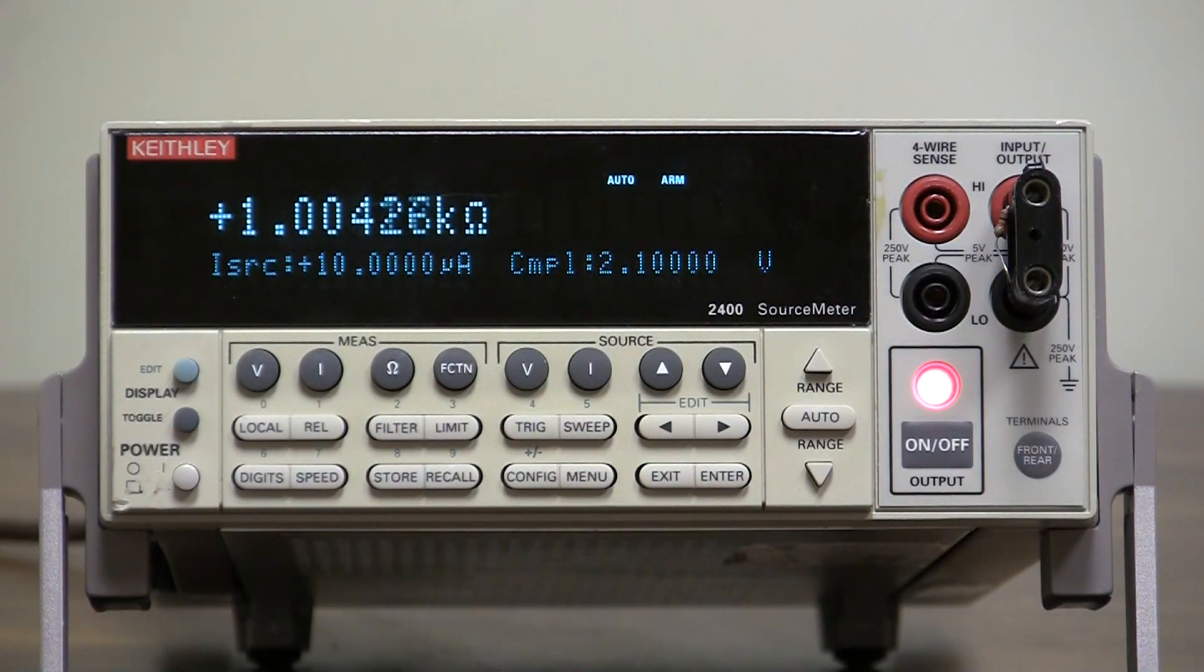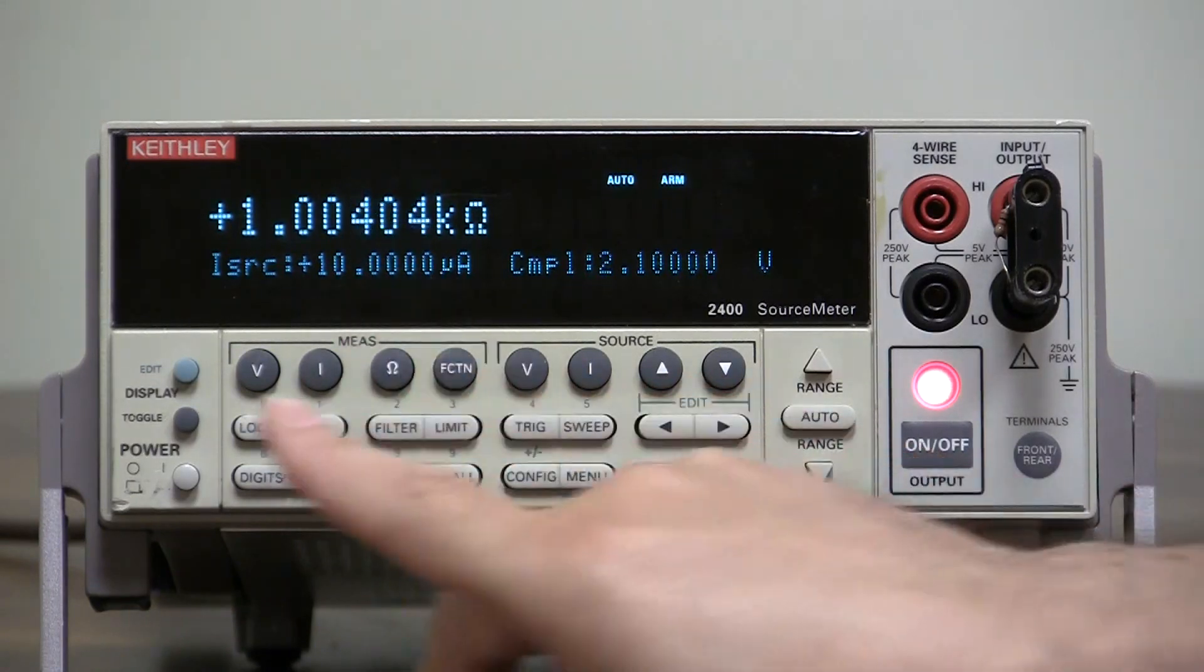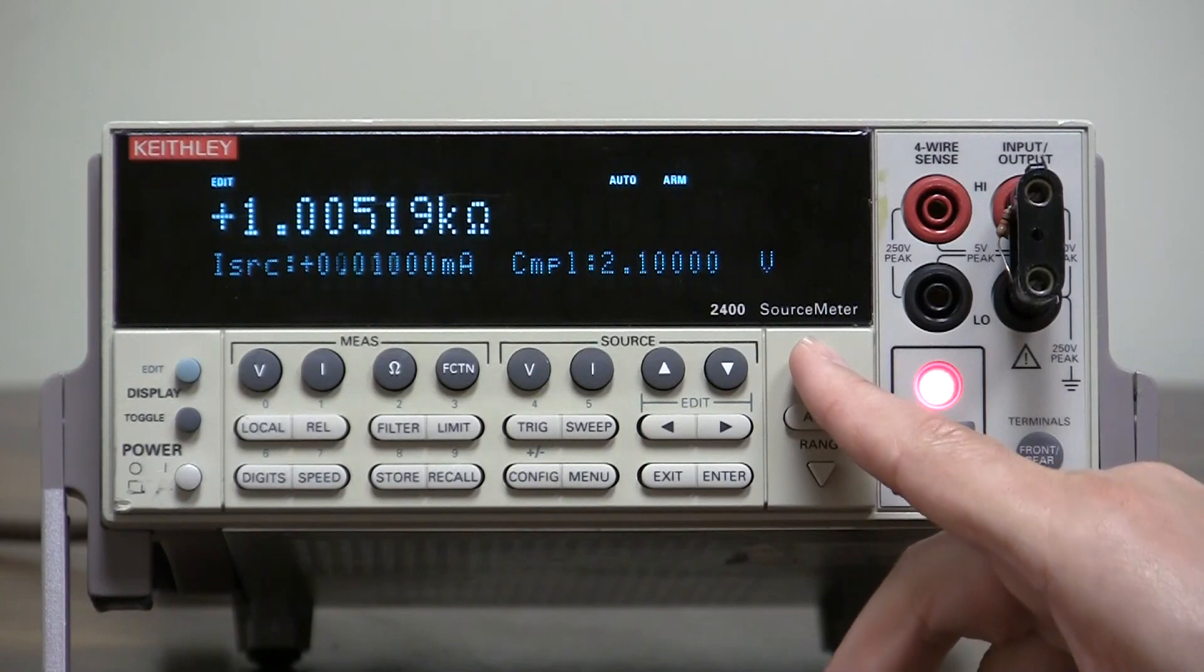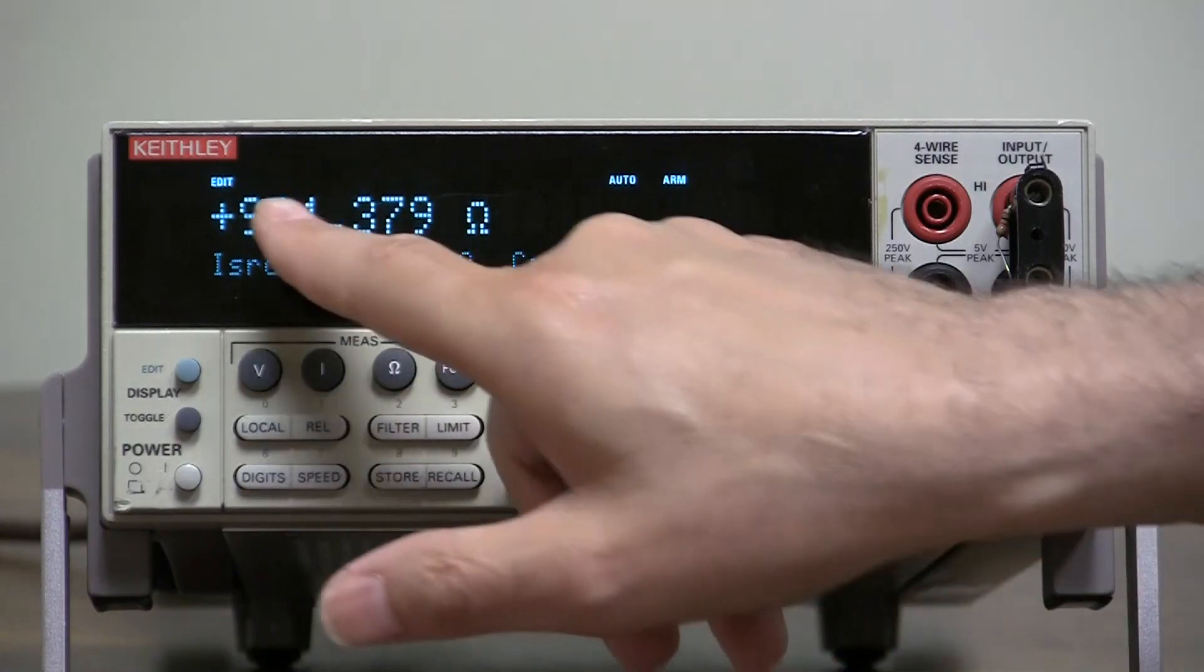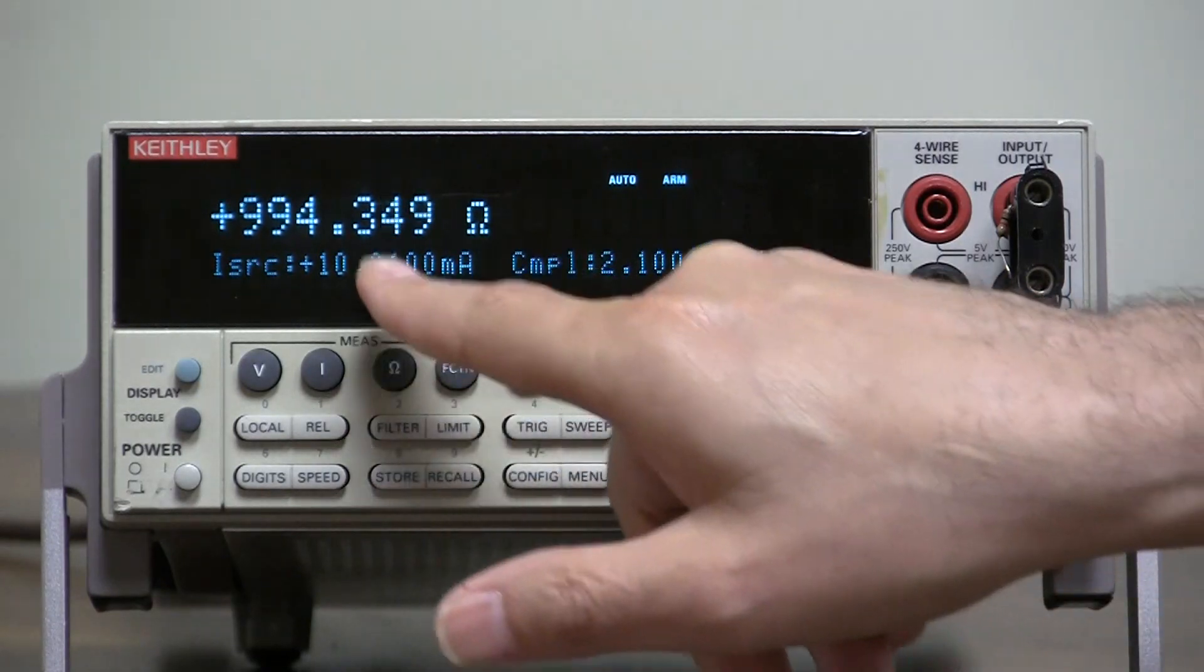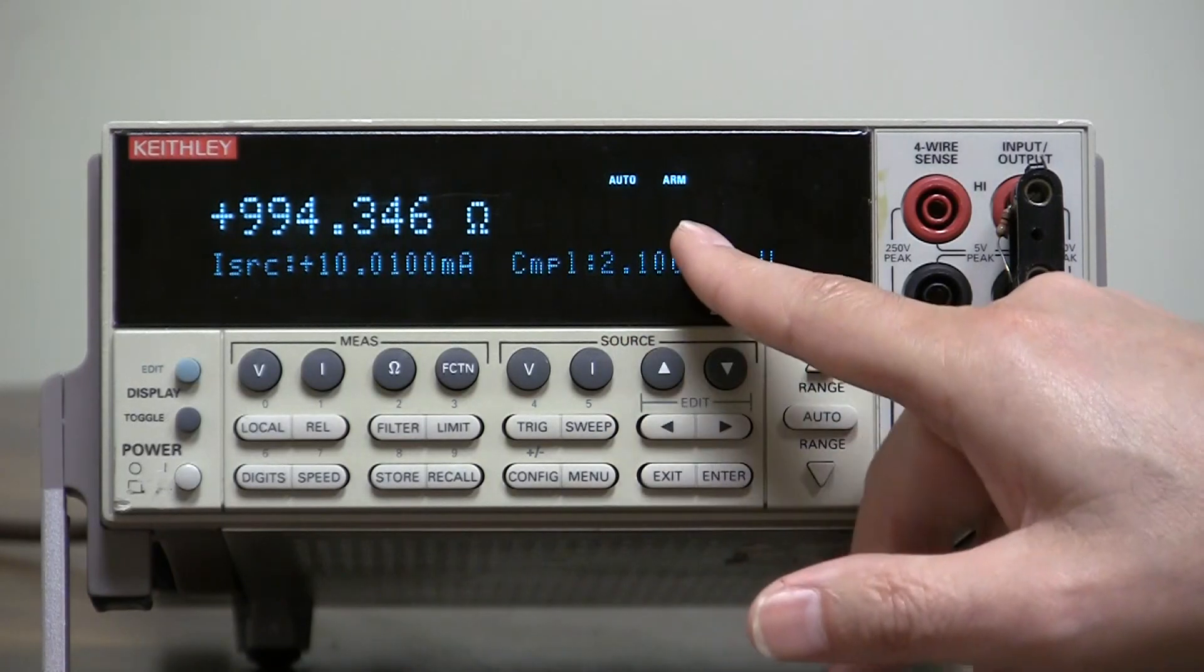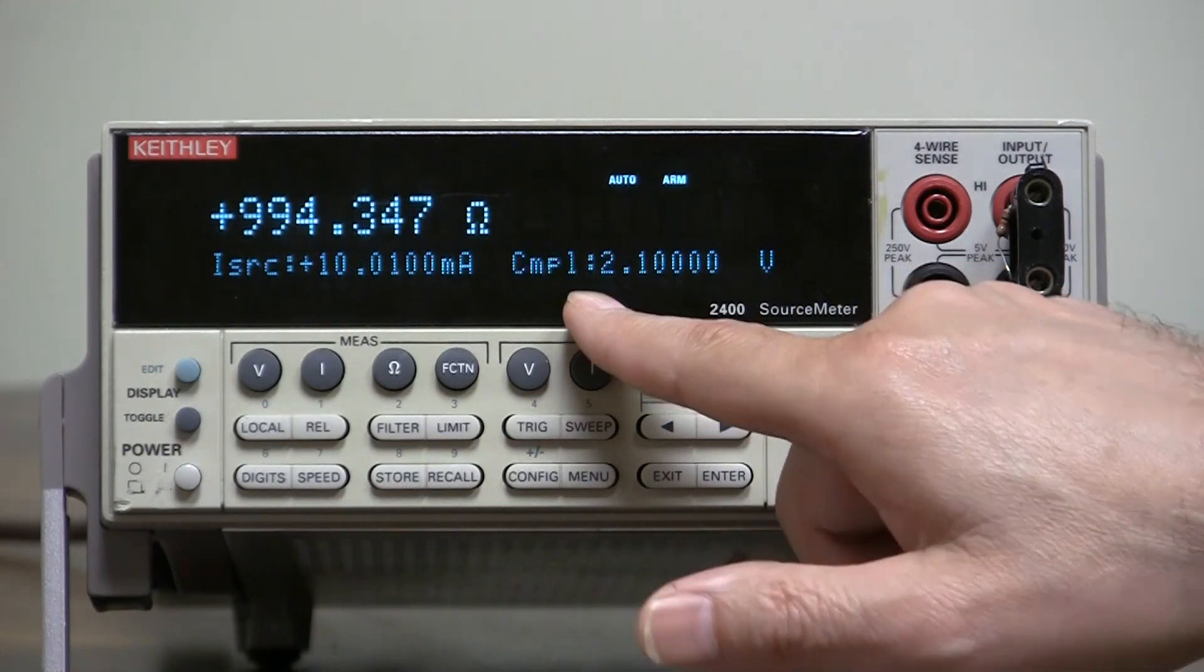Now, let's show real compliance. Real compliance is when we exceed this value here. So, to do that let's source a little more current. We'll press edit, up the range a little bit, let's go to maybe 10 milliamps. As soon as we do, look, the value goes down and this compliance is blinking. What it's trying to tell me is I'm trying to source 10 milliamps into 1K which would be 10 volts. It can't get there from here because of this 2.1 volts. So, the compliance is flashing trying to tell you that.